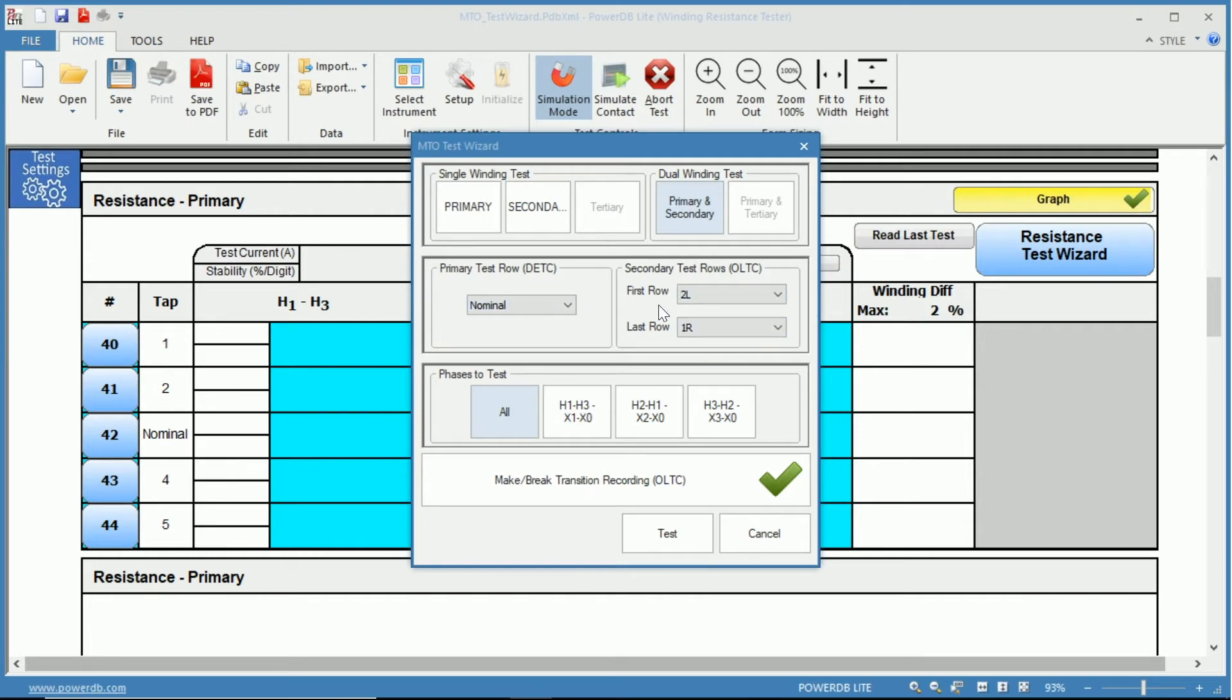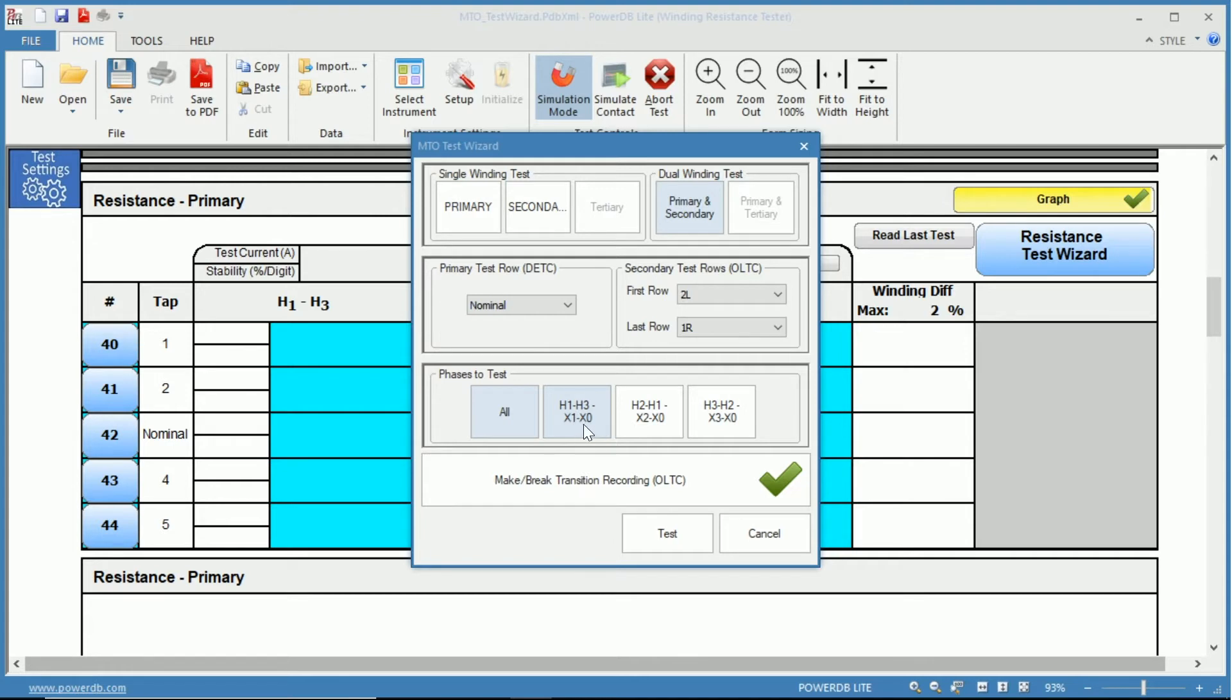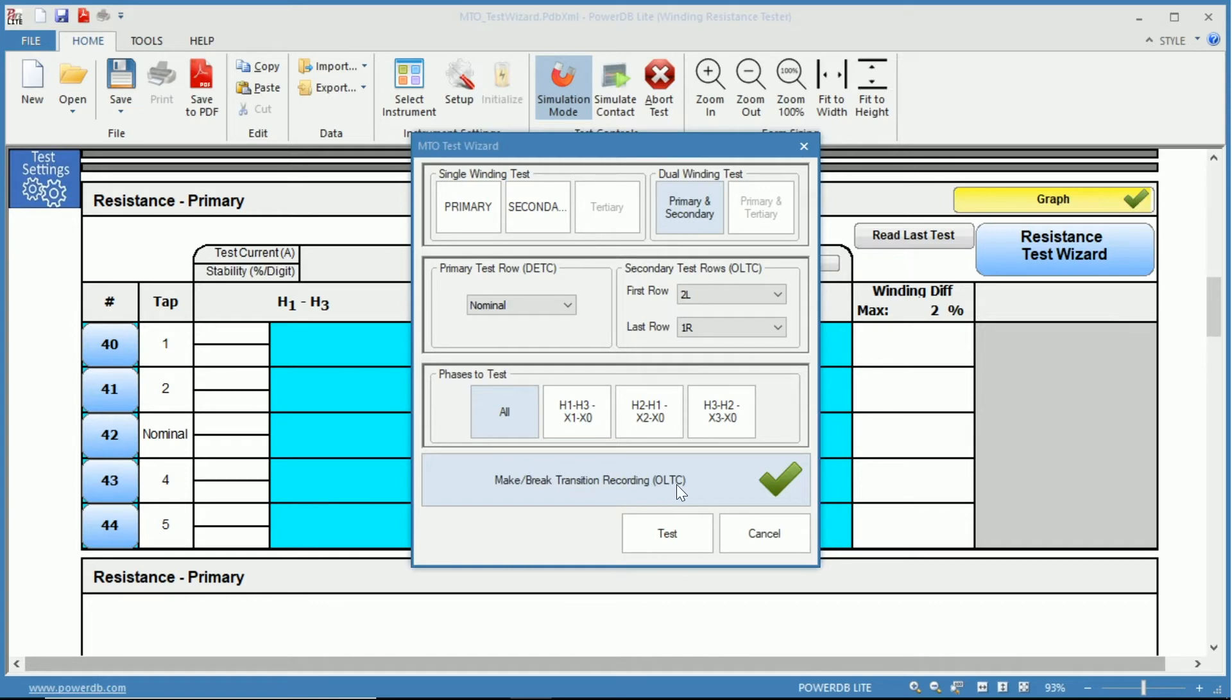Notice when choosing the phase to test, you have H1 to H3 as well as X0 or X1 to X0 on a single test. So you are testing your primary and secondary at the same time, and you also have again the make-before-break transition recording. Simply click to disable. If you have the check, you have it enabled.